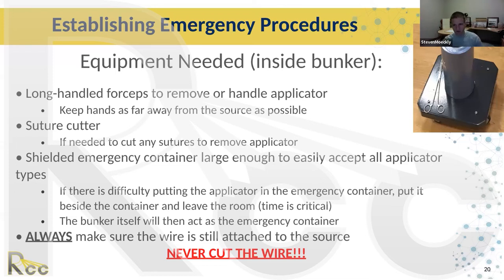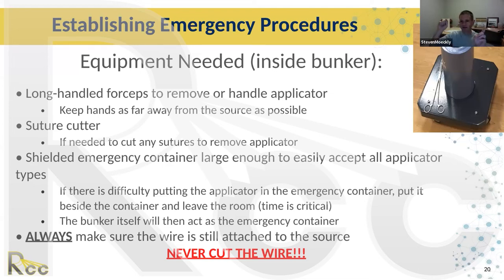Do not cut the wire. Historically some places included wire cutters in their kits — do not use them. If you're unsure of where the source is and you cut it, you could cut the source itself, creating a serious problem. If you cut it distal to the applicator, you now have a source still in the patient and unattached to the treatment unit. You want the source attached to the wire so you can remove it all together. I have yet to think of a situation where cutting the wire would be appropriate.